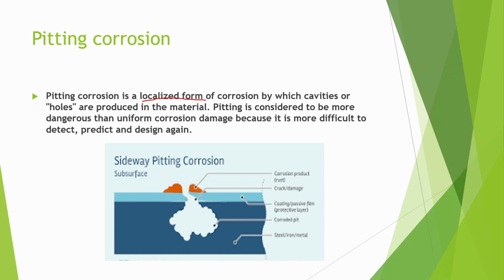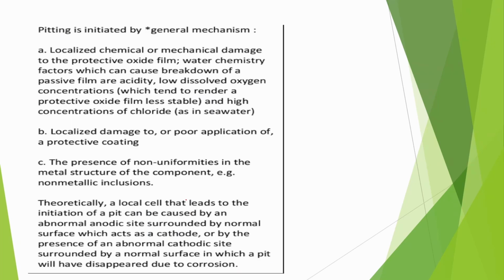So when the protective coating breaks, the base metal comes in contact with the external environment. After that corrosion starts. Evidence of pitting is usually found in the boiler shell around the water level and is mostly caused by poor storage procedure when the boiler is shut down for long intervals.